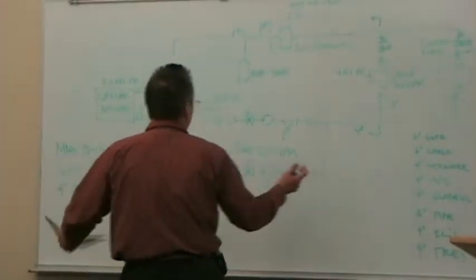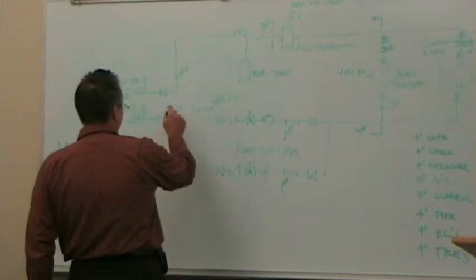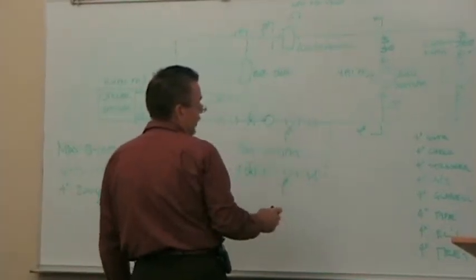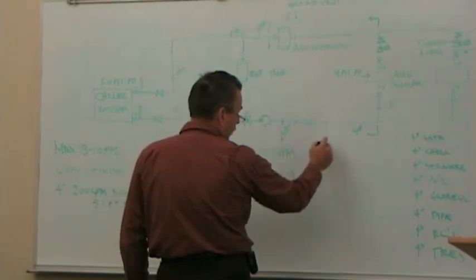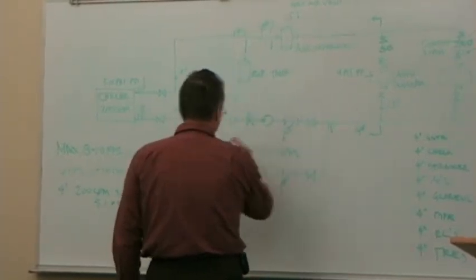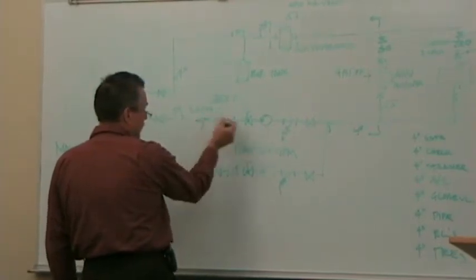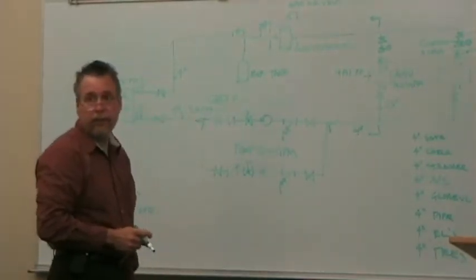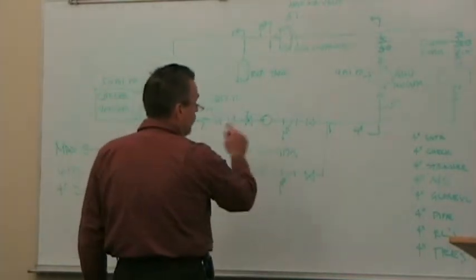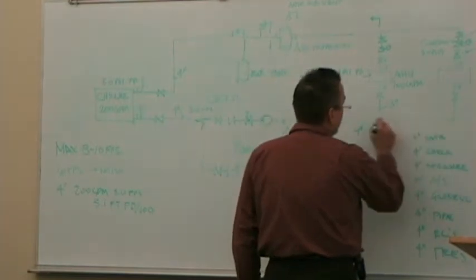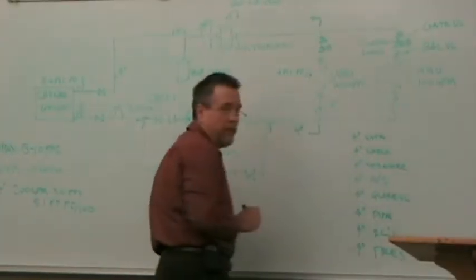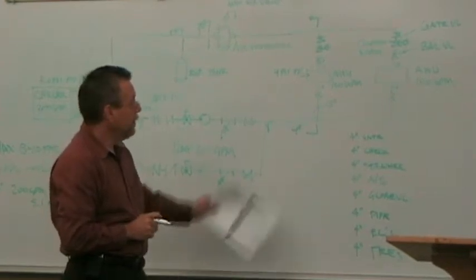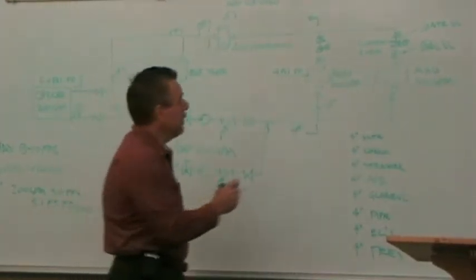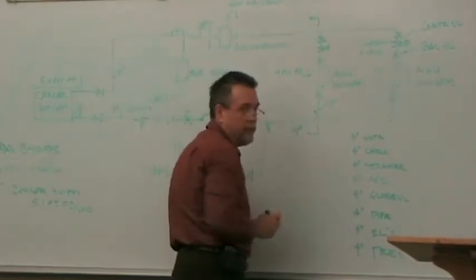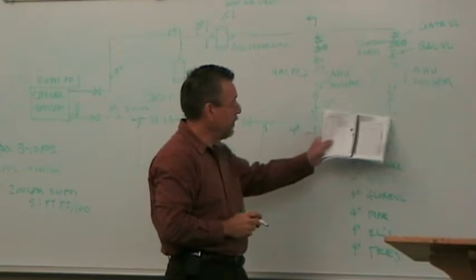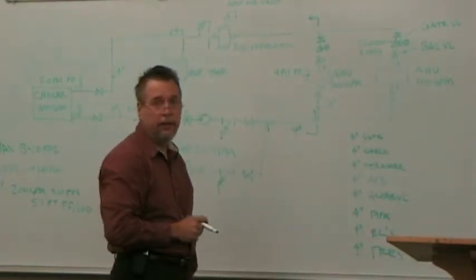So let's just say that I know that this is a 2D drawing, but I've got 1, 2, or I could take the worst case, I could go across T here to the elbow, across T there. That's going to have more pressure drop than that straight through T. And straight through T is not going to have any pressure drop at all. So I've got 1, 2 T's, and through experience, I might say that this is my design leg, assuming that all this piping is the same. Through experience, I might know that that cross T pressure drop is higher than that straight run of pipe and elbow, assuming that the air handling units are close together.